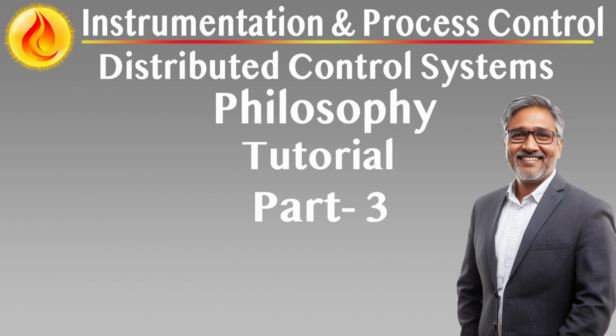Pulse-tested and monitored output circuits. All actuator outputs, deluge valves, fire dampers, solenoids, and audible visual alarms are pulse-tested for load health and integrity. Output status is verified through dual feedback mechanisms, typically current sensing and discrete position switches.